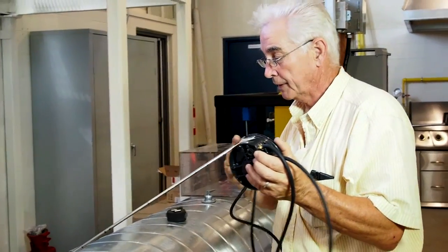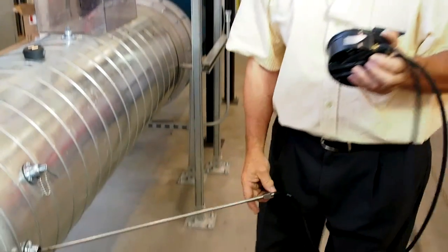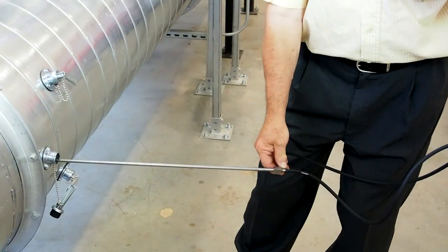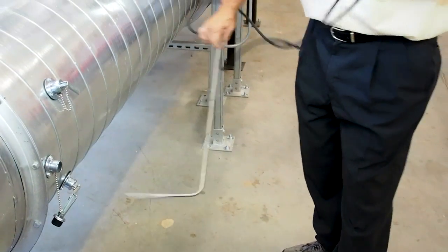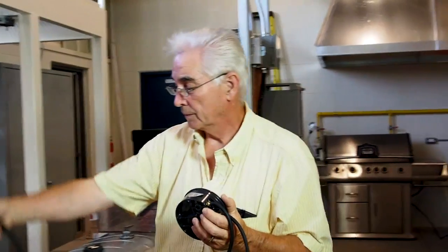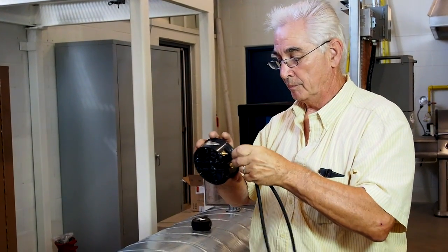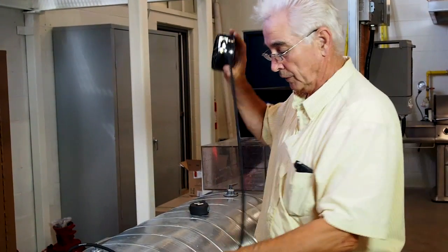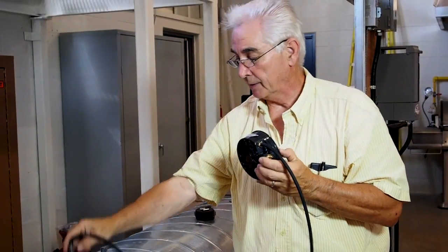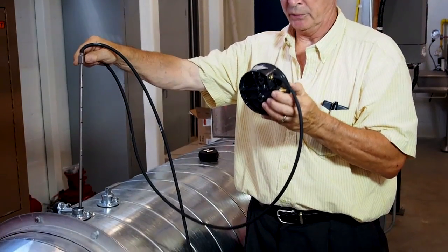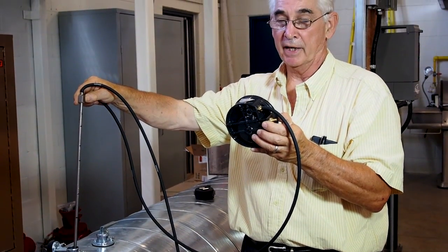We pull it out and measure at 90 degrees the same set of readings. We also record the static pressure by hooking up the static pressure tip to the upper port of the magnehelic and measuring about the center of the duct to see that the static is plus 0.25 inches right here.